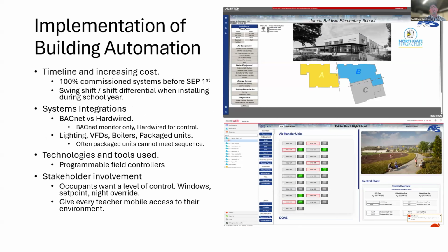Part of the implementation of building automation that we have to consider as a school district is when these new buildings come online, the systems have to be 100% commissioned before kids and teachers step onto site. If you've ever been on a construction site, schedules slip and the commissioning gets pushed down to 2 weeks and everybody's scrambling. So that's always a big challenge to make sure all these systems are operating. Peak efficiency would be great, but just maintaining temperature control is what we usually settle for, then fine tune it as the year progresses.